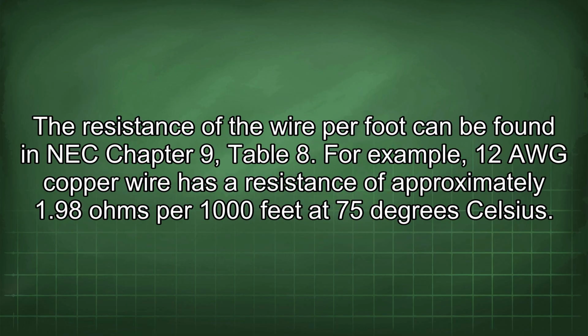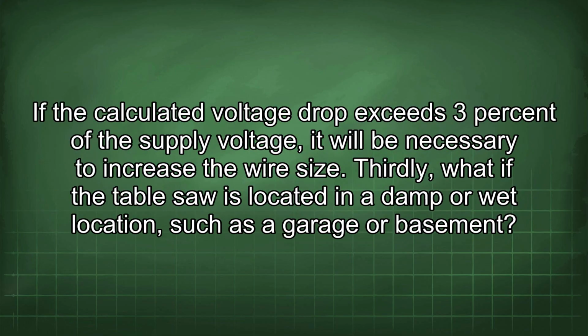The resistance of the wire per foot can be found in NEC Chapter 9, Table 8. For example, 12 AWG copper wire has a resistance of approximately 1.98 ohms per 1000 feet at 75 degrees Celsius. If the calculated voltage drop exceeds 3% of the supply voltage, it will be necessary to increase the wire size.